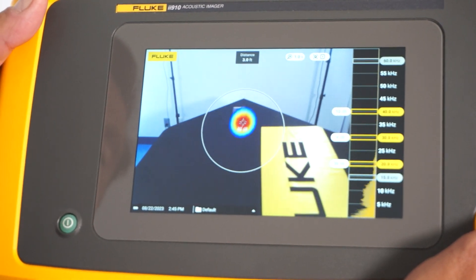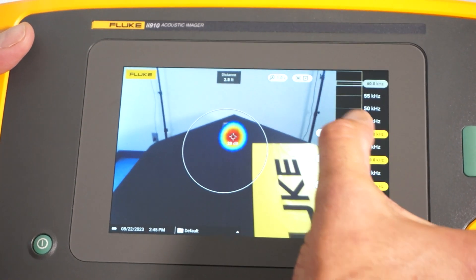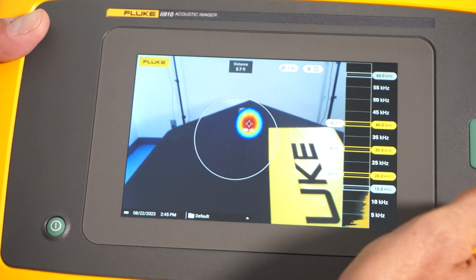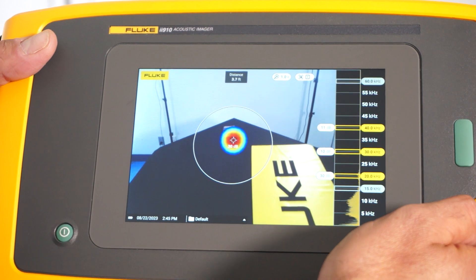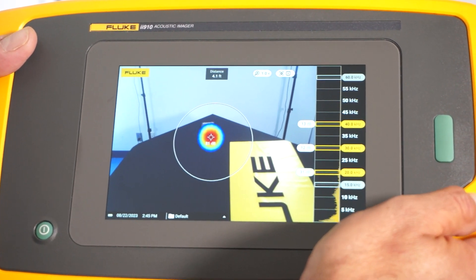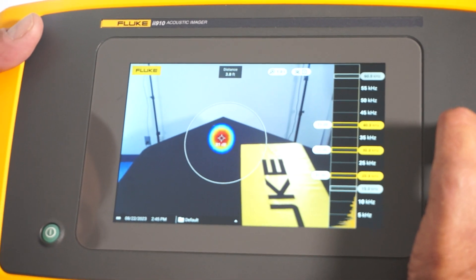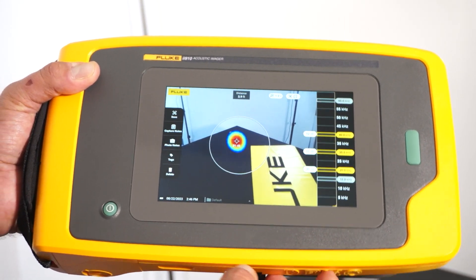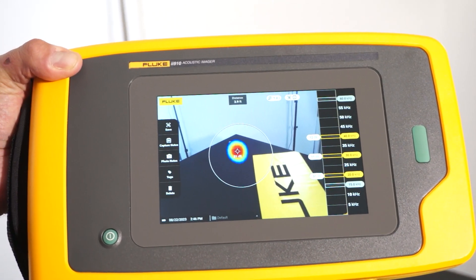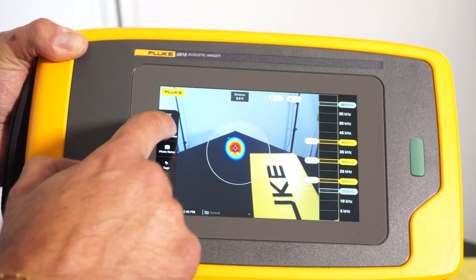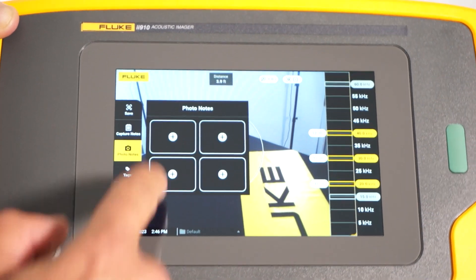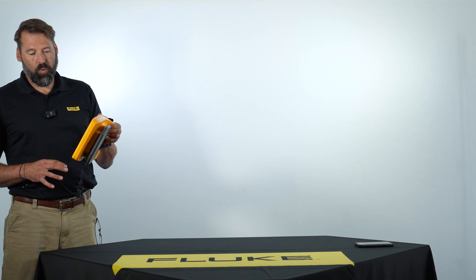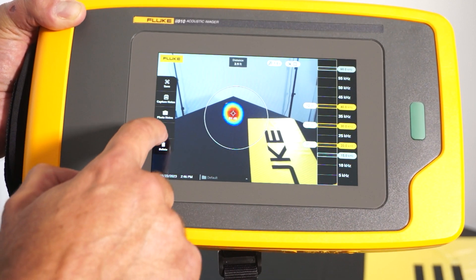I have my signal generator set at 20 kilohertz. At each frequency range I get a decibel scale, and at the 20 kilohertz range I'm picking up 20 decibels at a distance of roughly three and a half to four feet. I can hit capture and then go into the post-capture menus. Under capture notes I can type in any additional information I want. I can click on photo notes, turn on the camera, and take a picture of a nameplate on the particular asset.